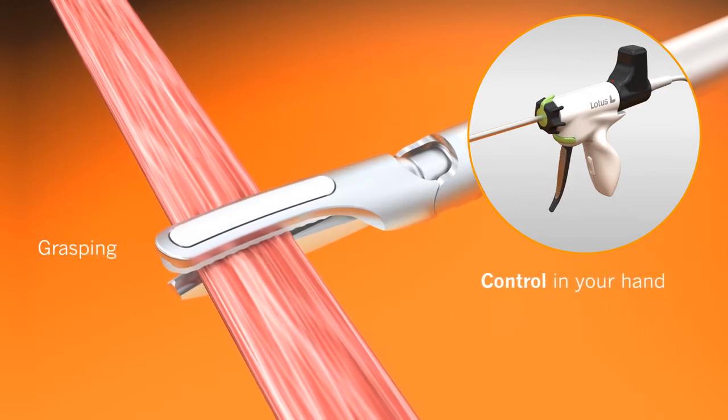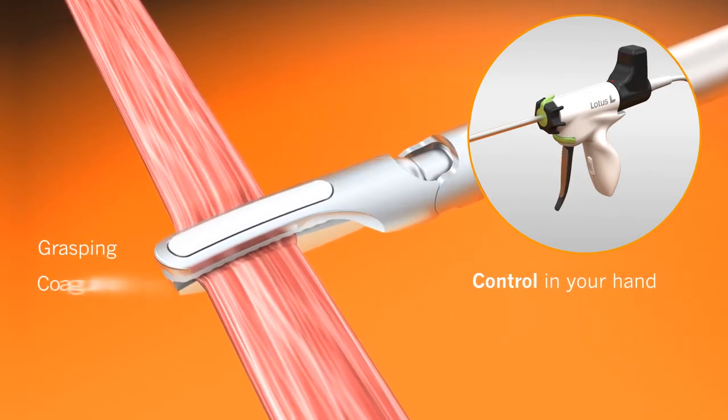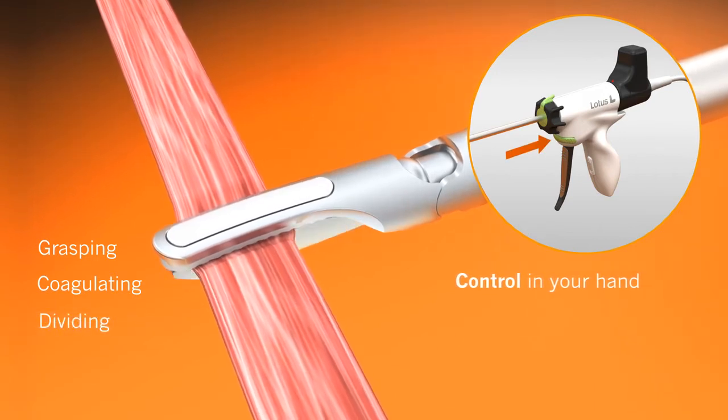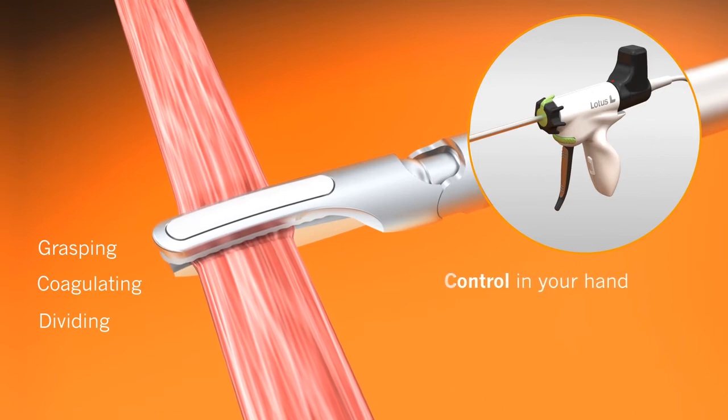Pressure on the handpiece trigger has a direct influence on the cutting speed of the Lotus ultrasonic scalpel. The high tactile feedback enables the surgeon to precisely control the dissection of the tissue.